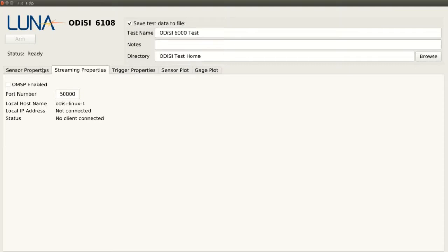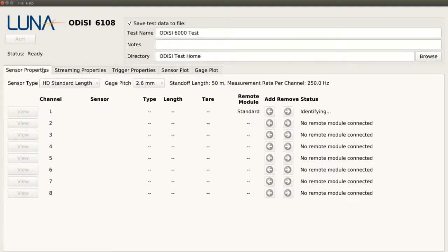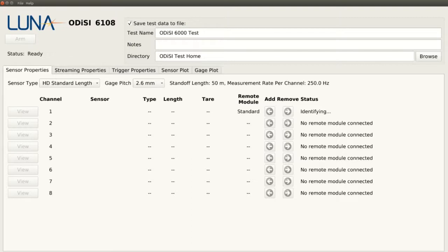Back at the Sensor Properties tab, we can see our available sensor channels and choose the gauge pitch, which determines the resolution mode that is used during a test. We can see the system is trying to identify the sensor at the channel that our aluminum beam is connected to. What we need to do first is install the sensor key that came with our sensor.